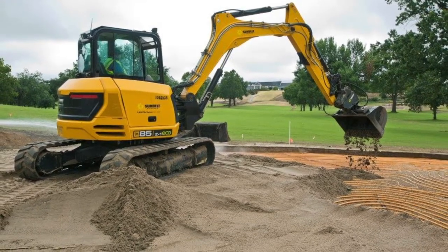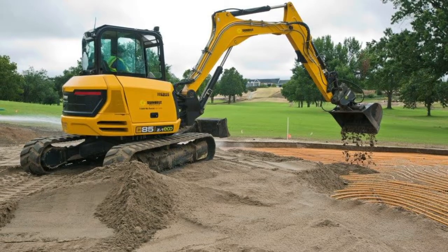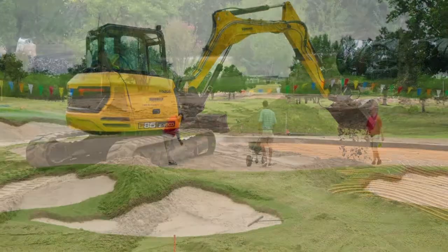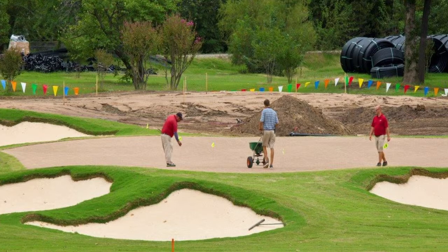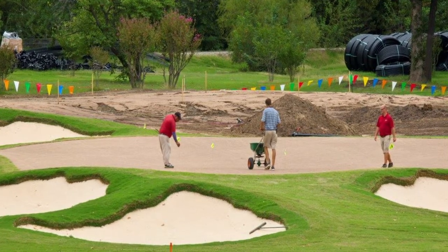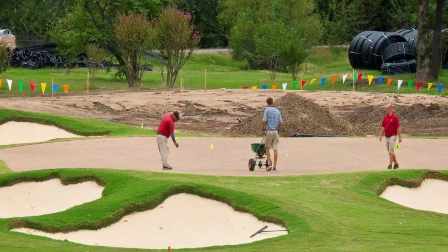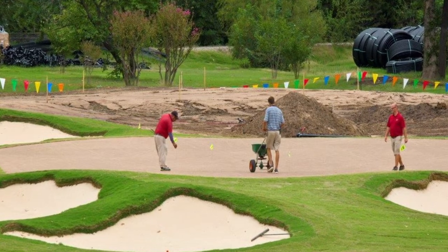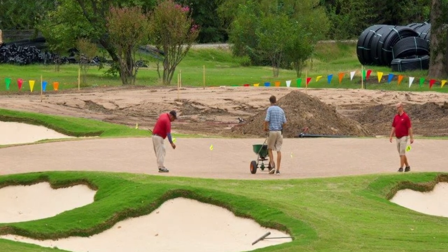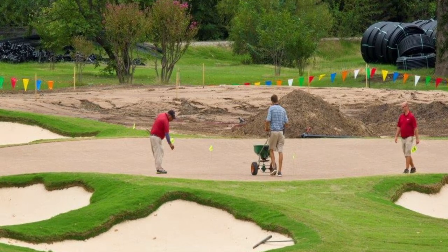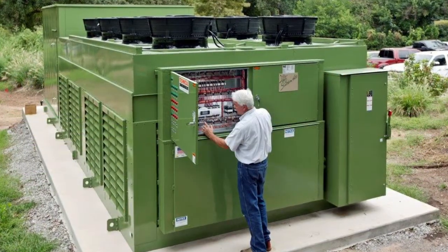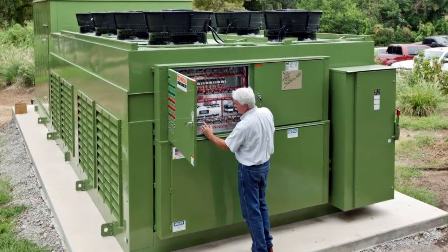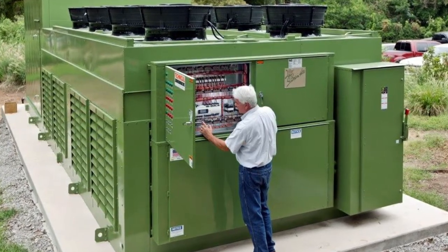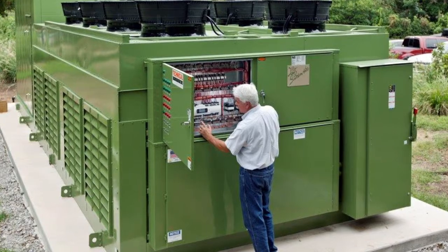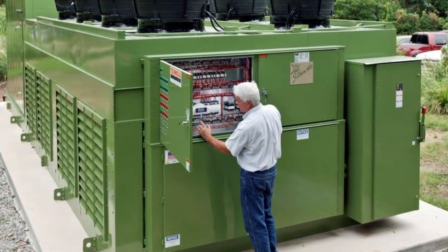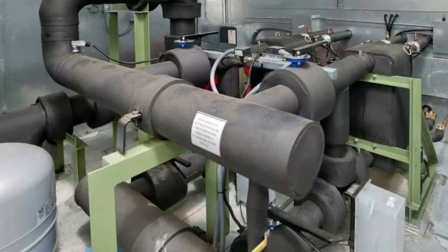Each unit contains multiple compressors and refrigerant circuits, modulating up or down to match a changing load. Fans are ECM powered, offering high efficiency, variable speed control, and low noise operation. Sound insulating covers were installed on the compressors and louvers, and off-site control is provided by a full DDC control system. Each of the 4 TSI air-to-water heat pumps also have an integrated variable flow pump located in an insulated cabinet, along with a brazed plate heat exchanger and control valves, eliminating outdoor pump skids or the need for separate mechanical rooms.